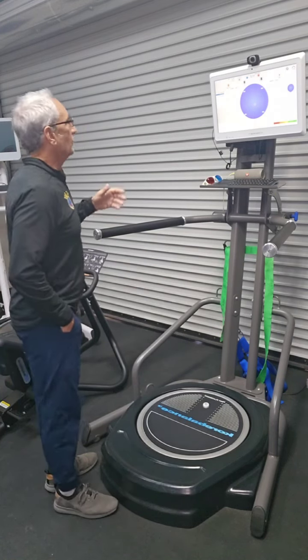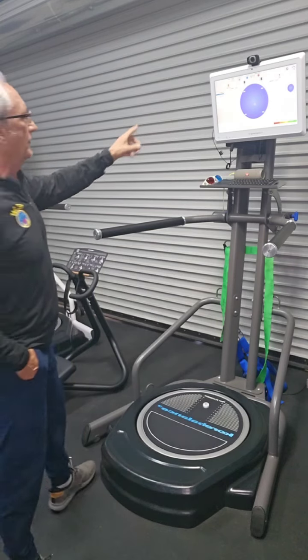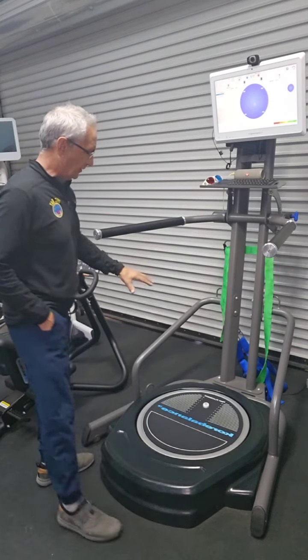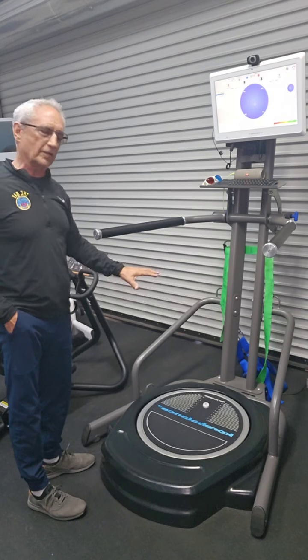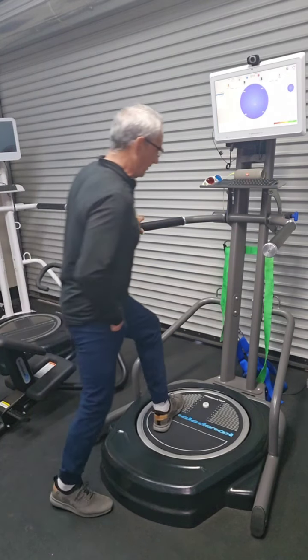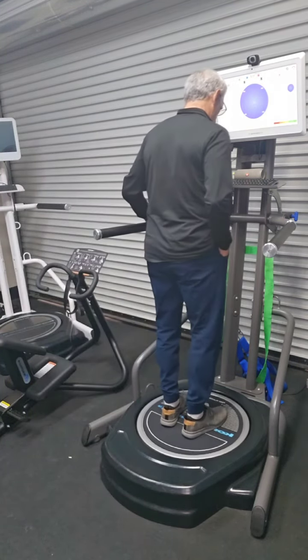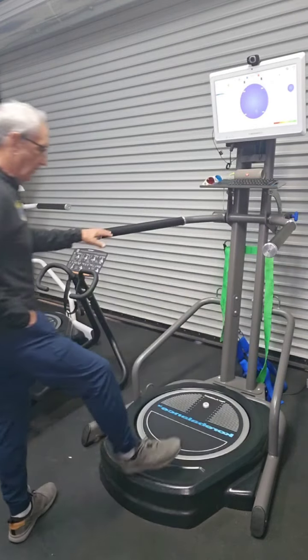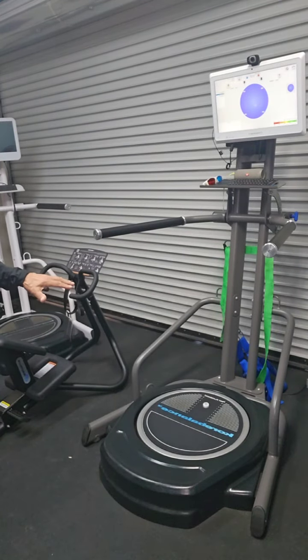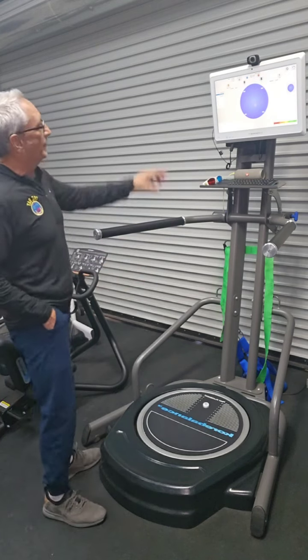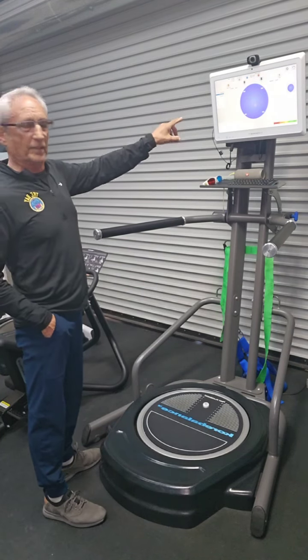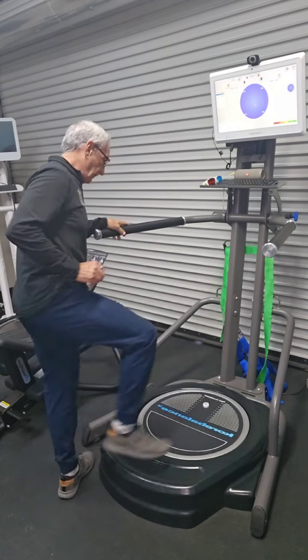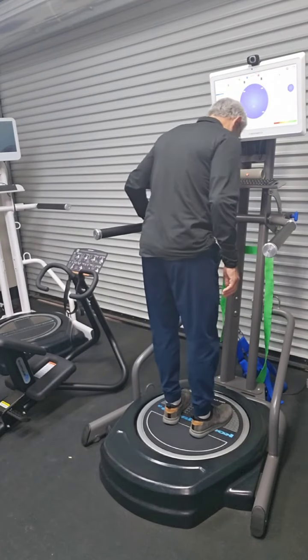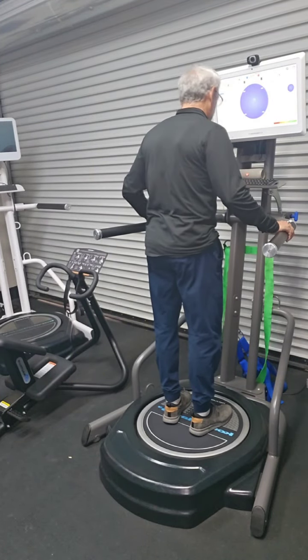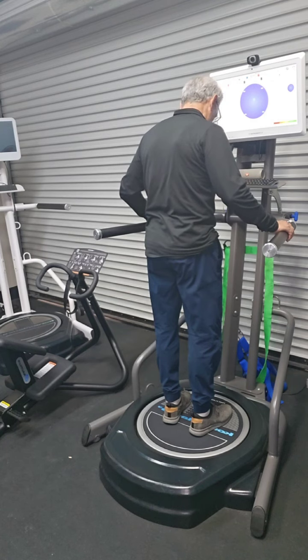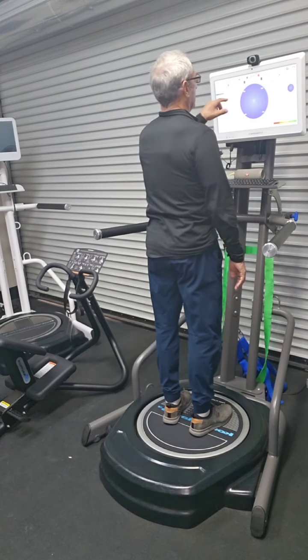Because some people will think because my target on the computer there is off, that the device may need calibration, and that's not true. What happens is this bladder has memory. So when an individual steps off the bladder, it's going to stay a little bit off center because of that bladder memory, and that will be reflected on the screen as well. But using a bubble level, I can get on this device, and then I can get the bubble level as close as I can to center, and that's going to keep my target centered.